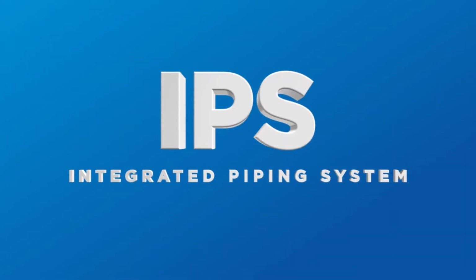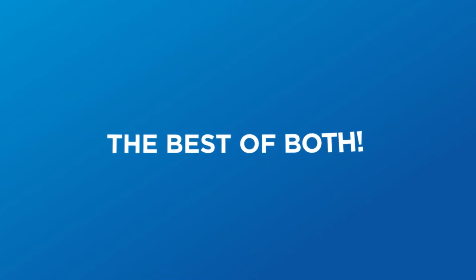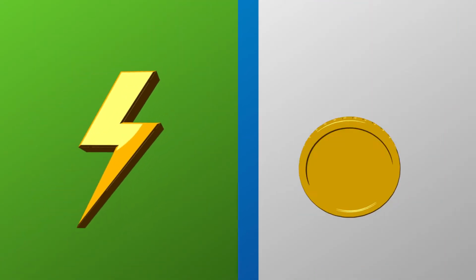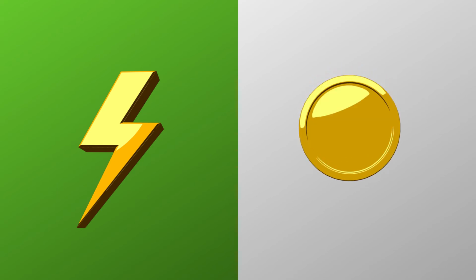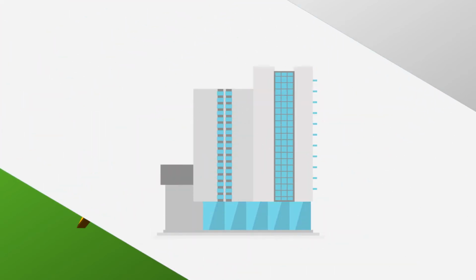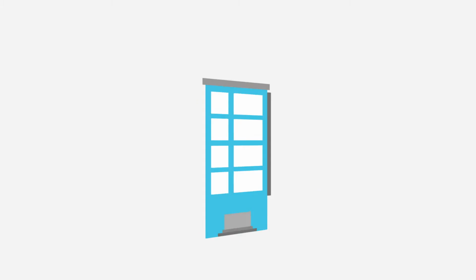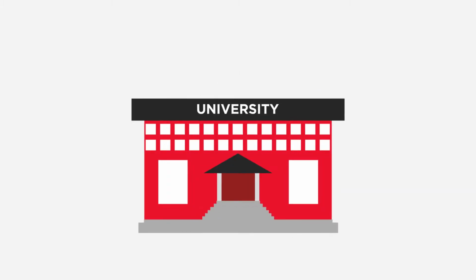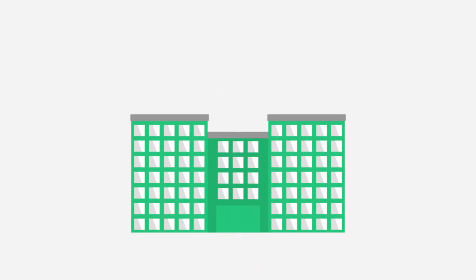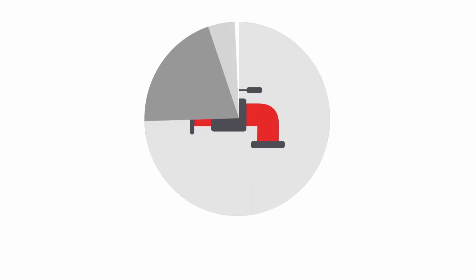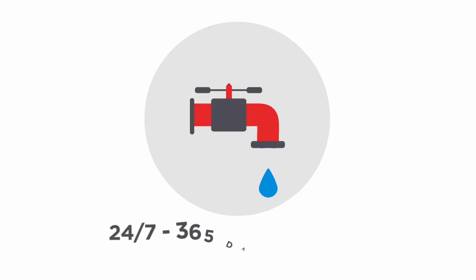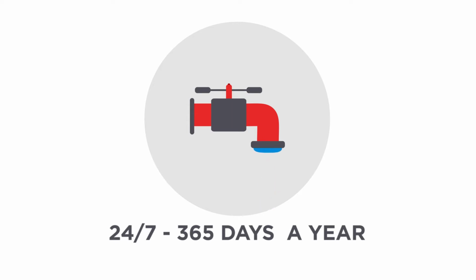With the integrated piping system, you get the best of both: the efficiency and energy savings of green and the affordability of a low-tech solution. IPS is suited for hotels, motels, condos, senior housing, dormitories, and apartment buildings. These types of buildings have a common thread. They all have central circulating domestic water because they house people and have a domestic hot and cold water requirement 24/7, 365 days per year.